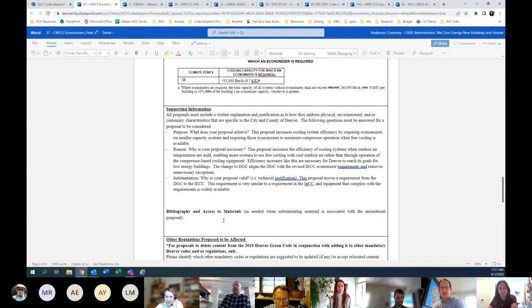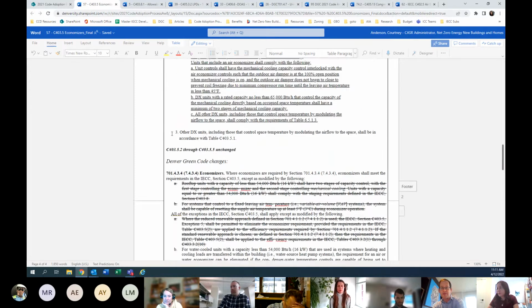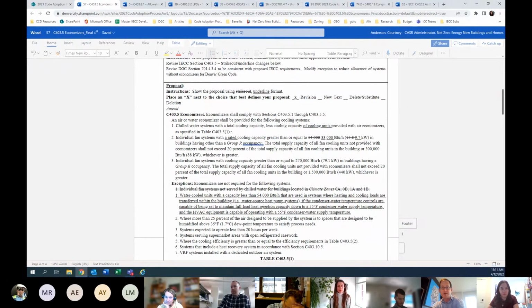Well, that's a good comment. A split system, certainly, when you start to get down to this size capacity, there's a lot of split systems available, some of which have higher cooling efficiency. So not only are we not looking to increase the required efficiency, we can't because of federal preemption typically. There are cases for some of these systems where a split system may be a better choice for that specific design, especially if the ventilation requirements are consistent and not too great. This is really comparing a unitary system, the one that provides heating, cooling, and ventilation, without an economizer with one that has an economizer.